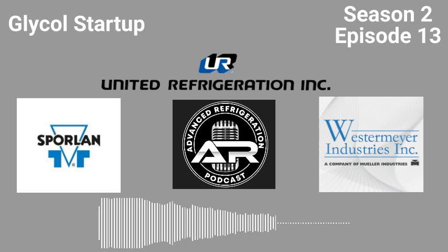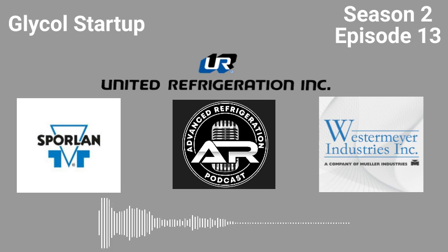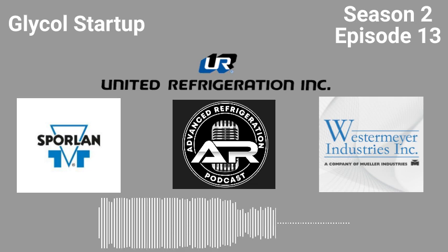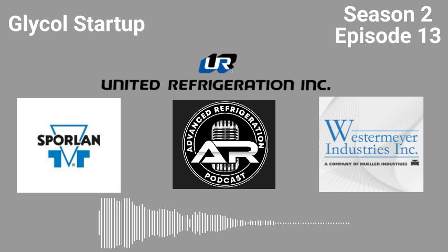If you have cases shutting off, your rack's running too cold. That goes for just about anybody. If you're cycling glycol solenoids nonstop, your rack's too cold. So you need to warm the rack up. The higher you keep the saturated suction temperature in the rack and the glycol temp, the better the rack is going to run. So just keep that in mind.